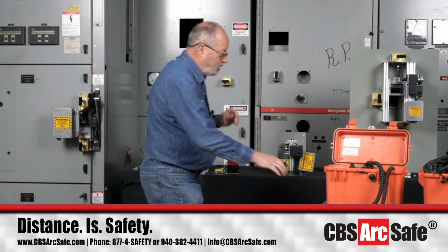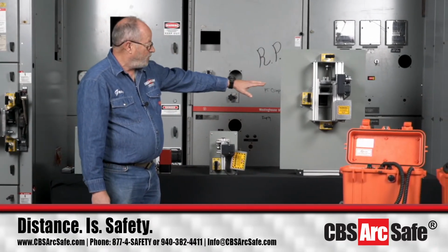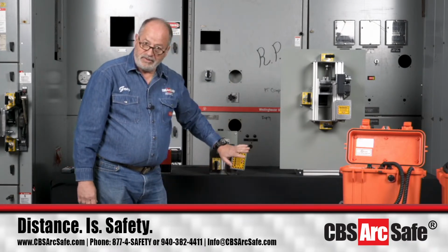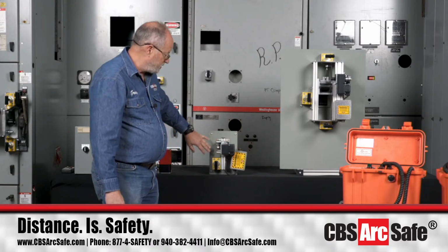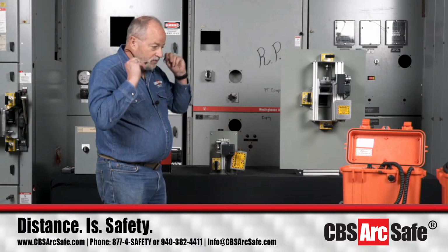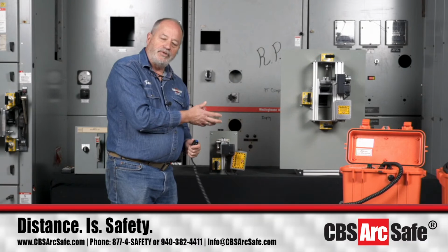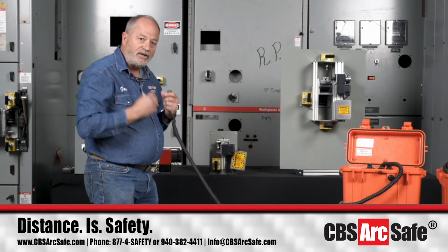The next thing we're going to look at are two molded case circuit breakers. Now the first one's just a little bitty sucker right here, and then we've got, I think it's an 800 amp size frame, Kyle? Yes. With the handle extension on it. So both of those are going to be operated by the RS01. Okay, and this would be like if it's mounted in a panel board or something, so it's mounted flush like this. I'll take it off after we've operated so you can see what we've got there and also here. With the one for the 800 amp Siemens ITE breaker, we did it with the handle extension, and the RS01 is built for this particular setup as if you had the lockout tagout on the right side so it would clear everything. So you'll see that when I take it off and I show you this also.